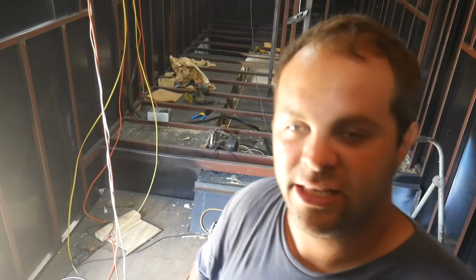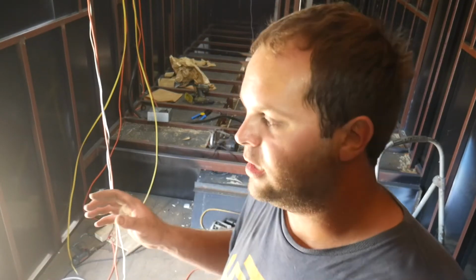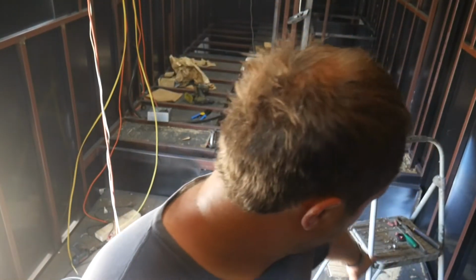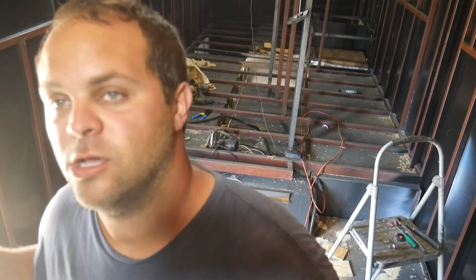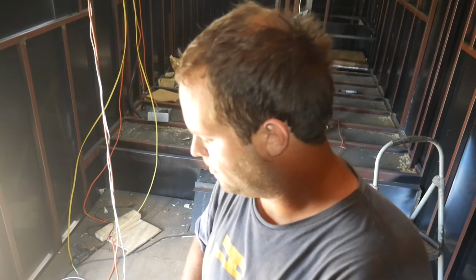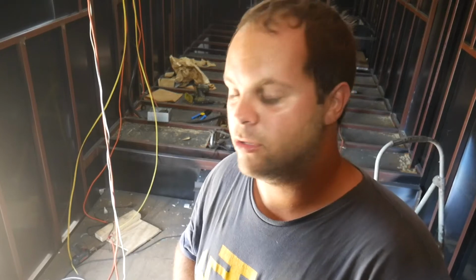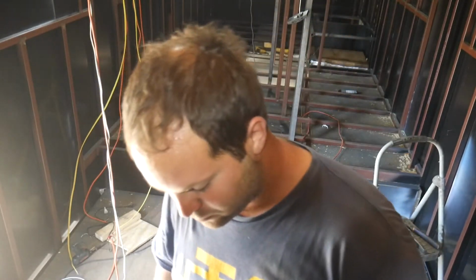Next, which will probably end this video, is I want to get my breaker box mounted. I'll explain where I'm going to put it. I want to temporarily bring my big cable in from the outside and hook it up to the breaker box. I'll go ahead and use the neutral in it, and I'll explain later why you need a separate one -- why you can't tie the neutral to the case as you typically would in a standard breaker box.